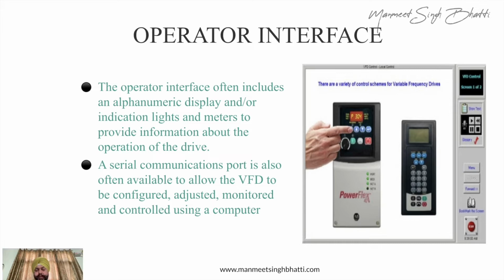Now this slide shows you the basic operator interface. This is standard with most VFDs, where you are able to program the VFD. You may want to do some kind of adjustment, see some displays of the parameters, or do some kind of control. The operator interface, as the name suggests, is used to control the complete variable frequency drive. The whole programming that needs to be done for the drive is done through the operator interface. It's one of the most important parts of a VFD.